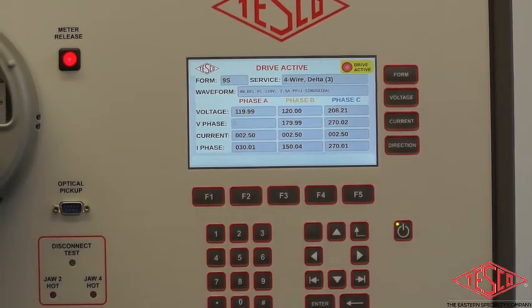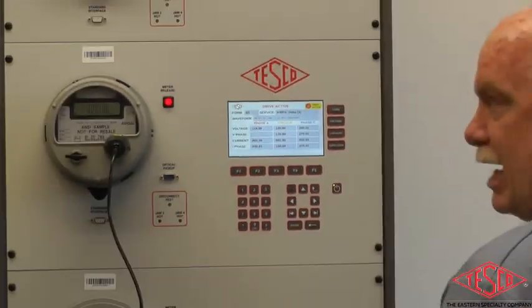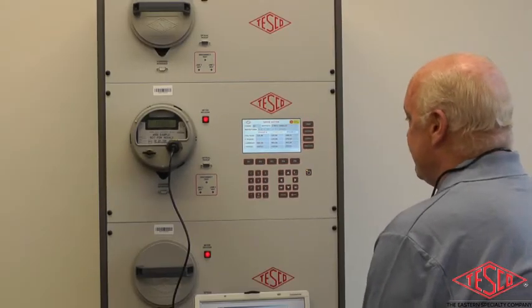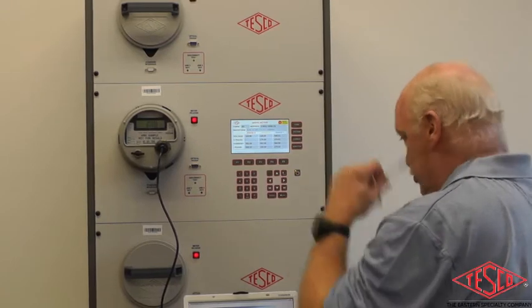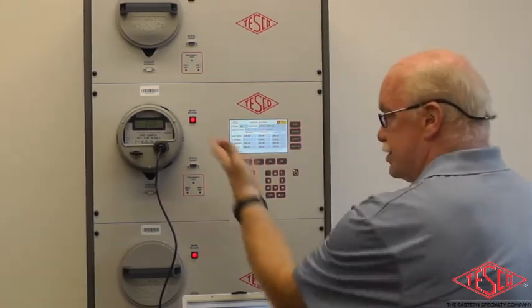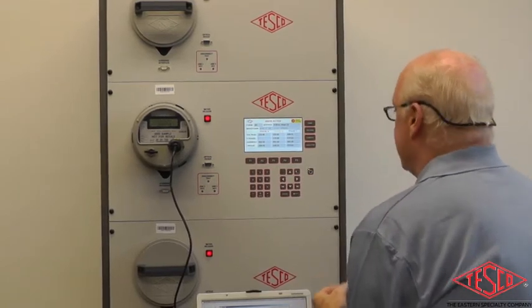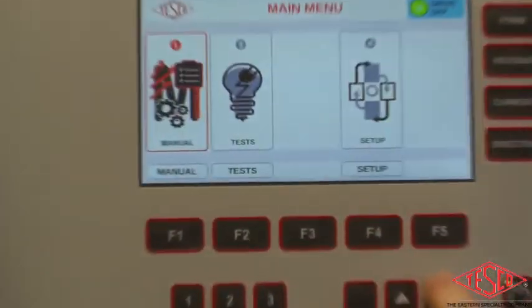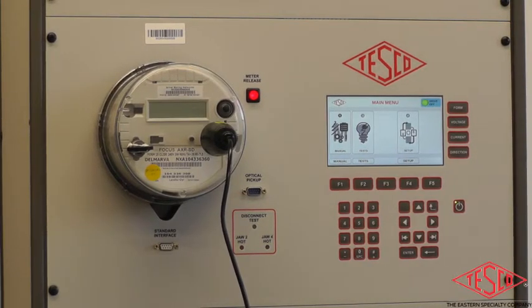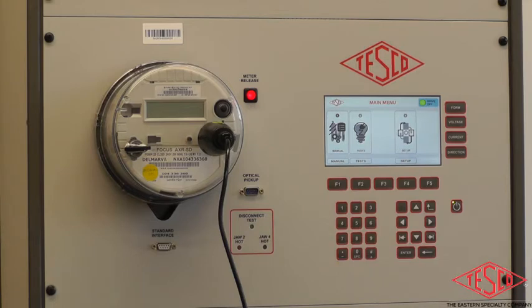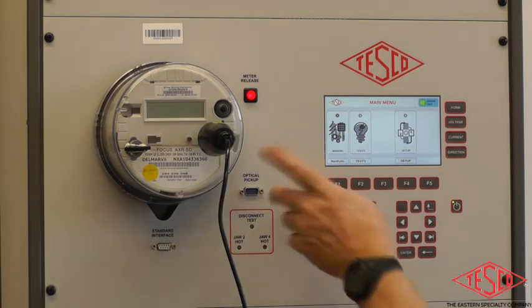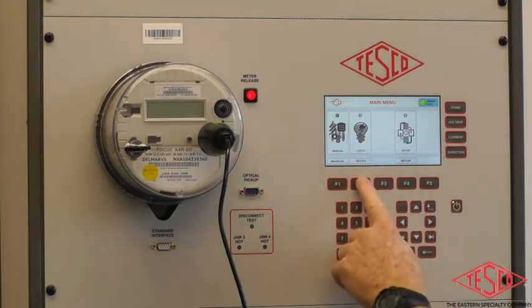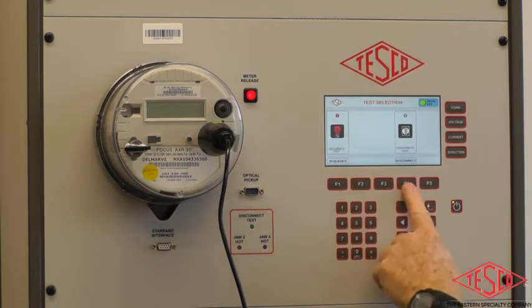So this thing will do 60 to 480 volts, 10 milliamps up to 50 amps in virtually any configuration, all automatically controlled. So you can do this same thing with almost any form, but I'll show you the most common form, Form 2, and we can run some disconnect tests. Okay, so we're doing the disconnect test, and in here I have a Landis & Gyr Form 2S meter along with the 1132 software, and I'll open up the disconnect function. So now I'm going to put the machine in the disconnect screen from the main menu tests, F4 disconnect, and then the form will be highlighted, go to Form 2S.